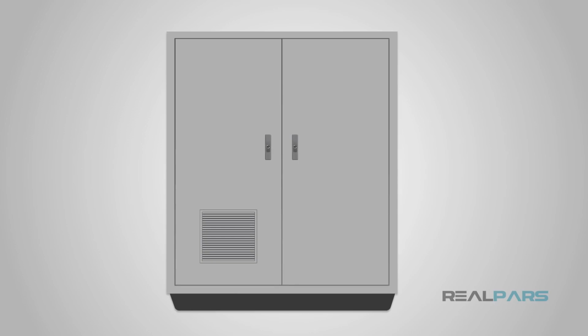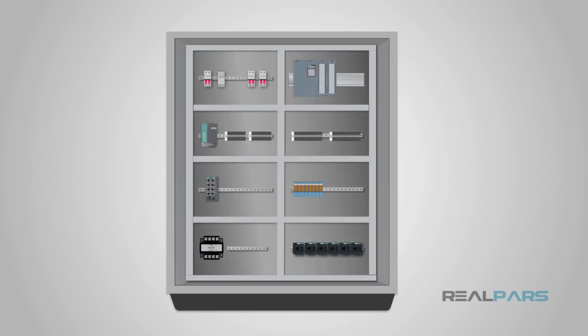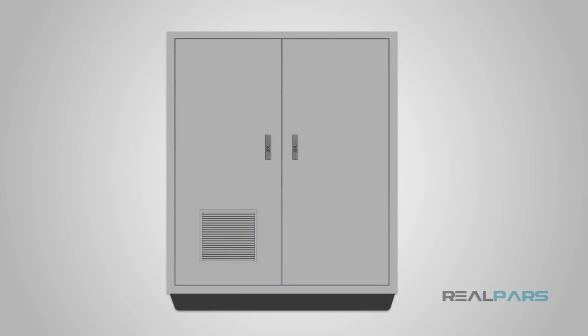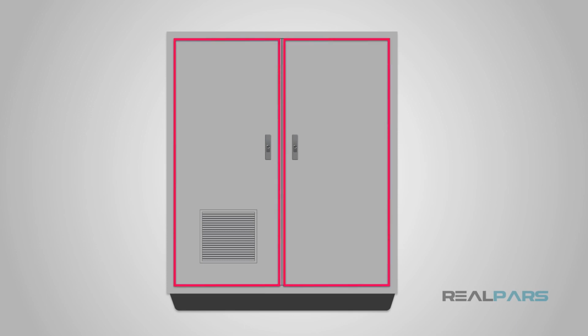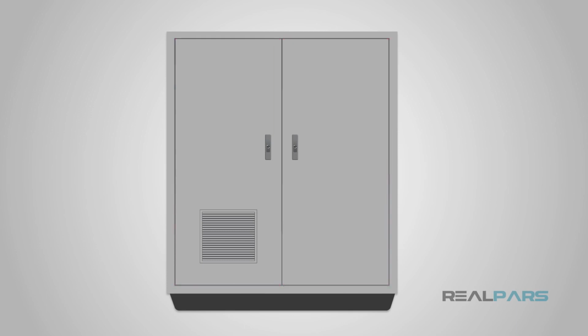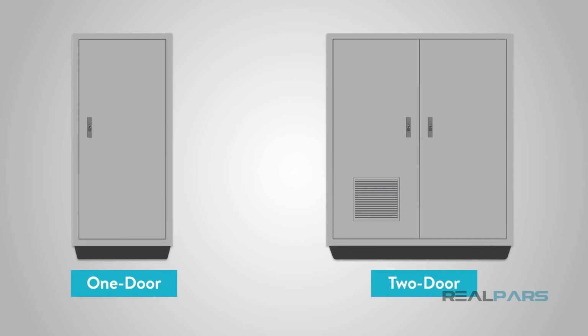Let's get started. First, let's talk about the enclosure, the metal box that contains all of the electrical devices of the control panel. Enclosures are often aluminum or stainless steel, and the size will vary based on the size of the process. A control panel enclosure can have multiple sections. Each section will have an access door. The size of the enclosure is commonly referred to by the number of doors the enclosure has.